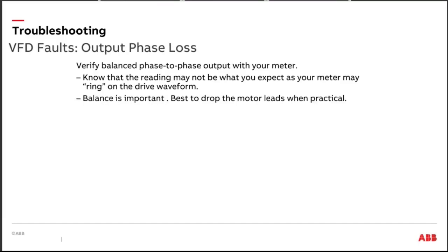Output phase loss. One more time, your meter is your best friend, okay? Now, if you're looking at the output of a drive, I typically tell people to run the drive up to at least half speed, okay? And I want to look at my output voltage phase to phase, not so much phase to ground, but phase to phase on the output of my drive. With some meters, depending on the type of meter that you're holding in your hand there, or you got sitting on your table or whatever, you might notice that your voltage is higher than what you're expecting. What you want to watch for is you want it to be balanced.